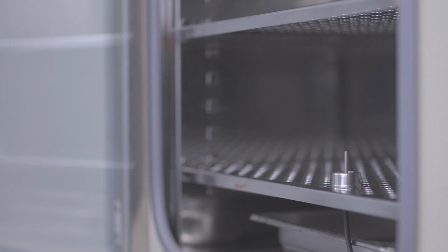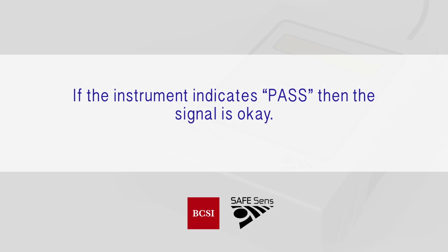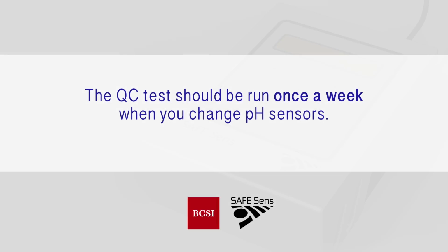The SafeSense quickly checks that the fluorescent signal still matches the initial factory settings and reports a confidence number close to 1,000. It may be off a little, but if the instrument indicates pass, then the signal is okay. If any differences exist, the SafeSense will automatically make the necessary internal adjustments. The QC test should be run once a week when you change pH sensors. Now we are ready to start the site standardization protocol.